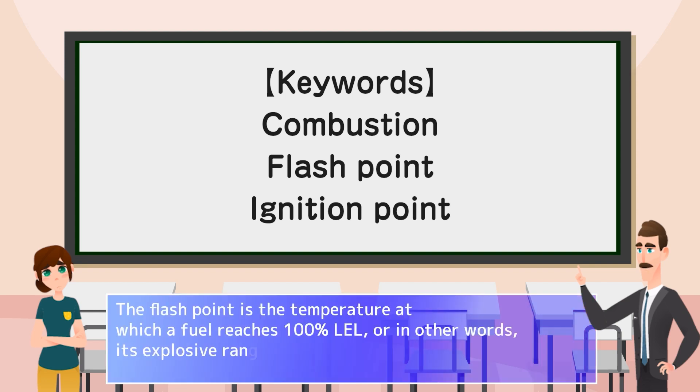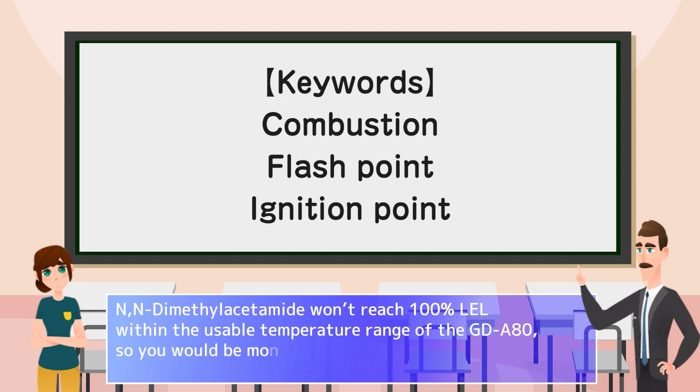The flash point is the temperature at which a fuel reaches 100% LEL, or in other words, its explosive range. N,N-dimethylacetamide won't reach 100% LEL within the usable temperature range of the GDA80, so you would be monitoring it at a lower concentration.